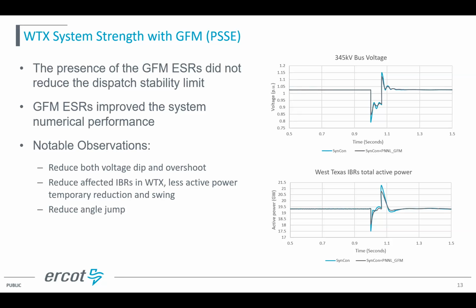If you look at the top right plot, it is the 345 kV bus voltage, the average bus voltage in West Texas. As you can see, when we have a fault, the voltage will dip. We have two curves: one is synchronous, and another one is synchronous plus grid forming. With grid forming, the voltage dip during the fault is reduced a lot. To me, that means we probably will have fewer IBRs entering VRT mode, which potentially leads to fewer unit trips, because usually when an IBR unit enters VRT mode it could trip. So if fewer IBRs enter VRT mode, we will probably have fewer IBR trips. Also, immediately after the fault is cleared, we have voltage overshoot, and with grid forming, the overshoot also improved.